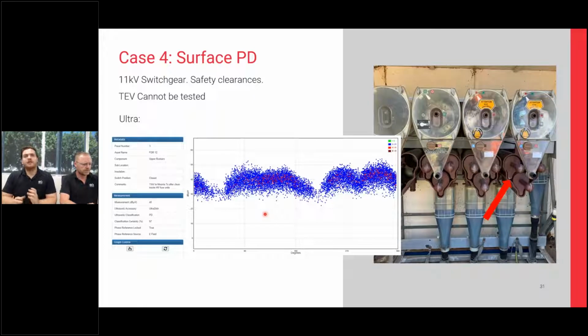This one's a little bit more in depth, and it's what you get once you start to have two sources of discharge on separate phases on the same asset. So these are your HV fuses on a quite old RMU, and you can see at the bottom right here this white powder of the discharge occurring between the two insulation layers. Now it was occurring here and also on this fuse over here at the exact same point.